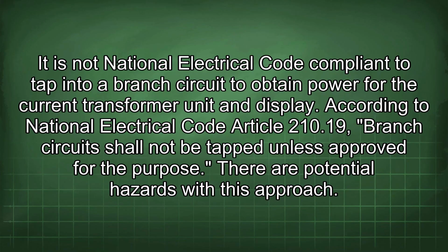It is not National Electrical Code compliant to tap into a branch circuit to obtain power for the current transformer unit and display. According to National Electrical Code Article 210.19, branch circuits shall not be tapped unless approved for the purpose. There are potential hazards with this approach.